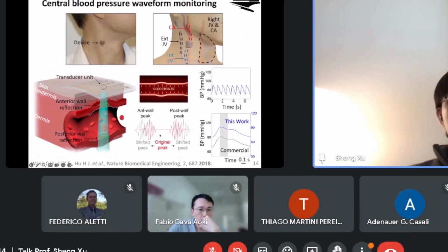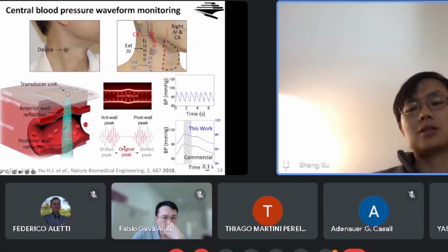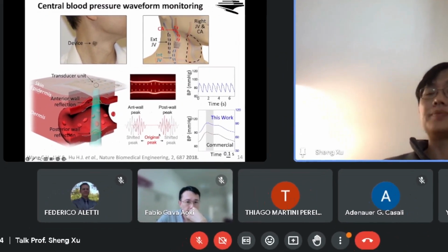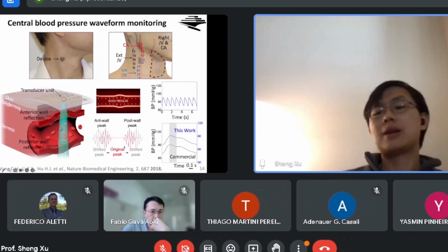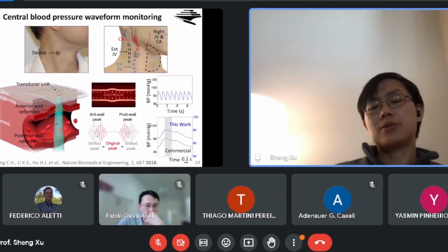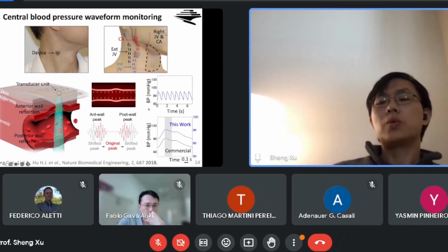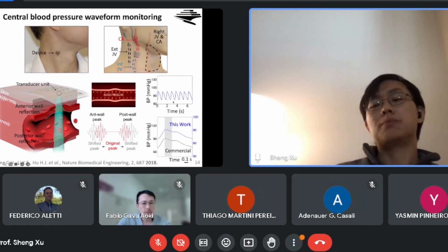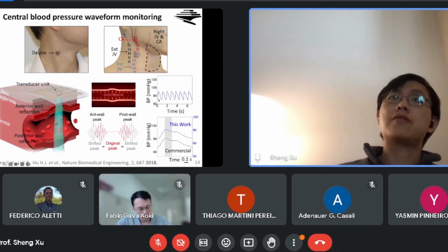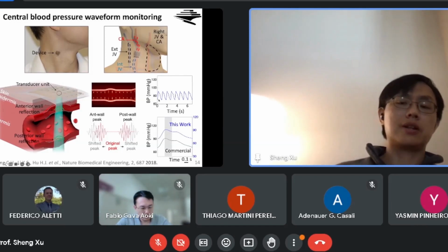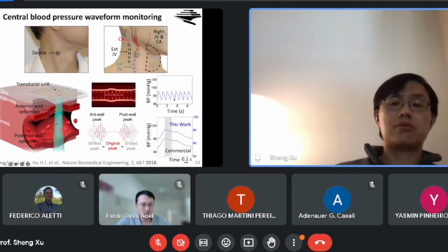So that means those reflection peaks will shift back and forth in position. By monitoring the distance between those two reflection peaks, we are measuring the vessel diameter. Through a series of well-established equations and the calibration, we can convert the vessel diameter into blood pressure, and we can transmit 5,000 pulses every second in the human body. So we can record the blood pressure waveform at a very high temporal resolution.